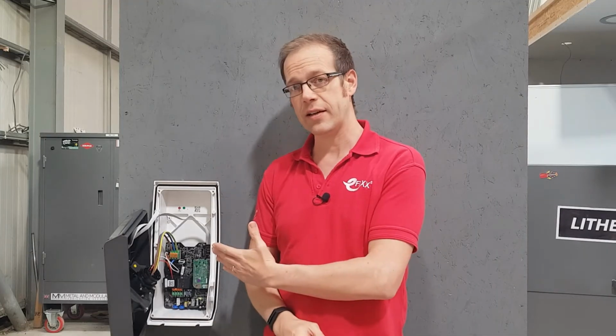So, to translate, in this method, a device monitors the voltage between the circuit protective conductor of the EV charging unit and earth, remembering that is the literal earth that we walk around on. Now this makes sense because the CPC of the circuit is effectively connected to the bodywork of the car. So what this method is doing is measuring the voltage that could reasonably be expected to appear across a person touching the car and the literal earth. If this value goes over 70 volts, it will disconnect the circuit in less than 5 seconds.